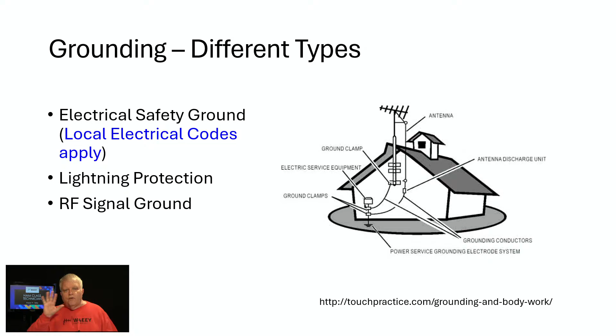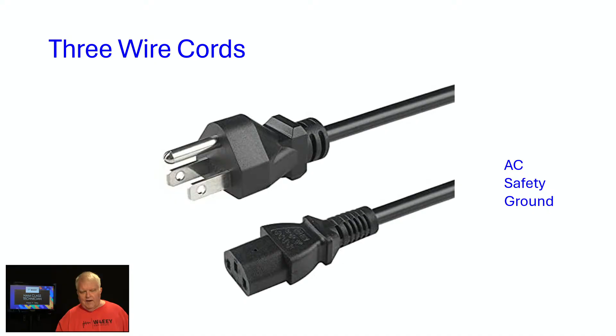And for safety ground, 3-wire cords are always recommended. It's this big prong out here that is the safety ground for equipment. This goes to the green wire in the cord and all the way back to the main circuit breaker panel. So 3-wire cords provide you with an AC safety ground.